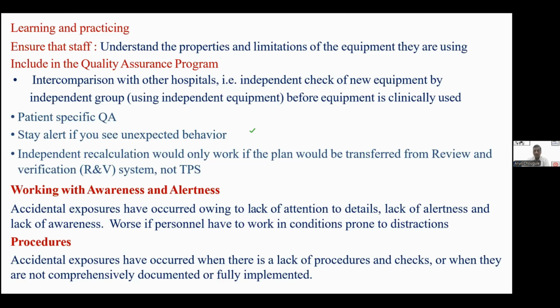So we have to do audits, and the IAEA has also suggested audits of equipment by an independent group before the equipment is clinically used, or after repair when we are going to use it again, or when we start any new protocol; we first have to understand everything. Patient, not only equipment, because with IMRT and IGRT, patient-specific QA is very, very important. Stay alert if you see unexpected behavior. This applies to RTTs, medical physicists, and radiation oncologists, because they observe during patient follow-up. For example, if radiation is given for a brain tumor and there is hair loss on one side, oncologists can observe it, then talk to the physicists and RTTs to see whether anything is going wrong. Independent recalculation would only work if that plan is pushed through for treatment, and not from the TPS treatment plan.